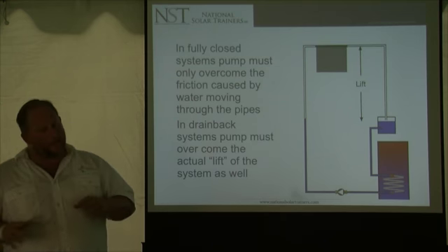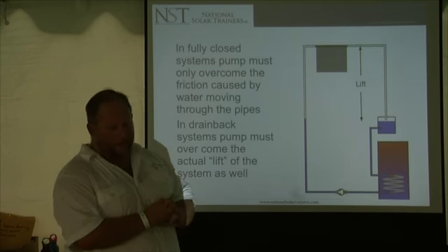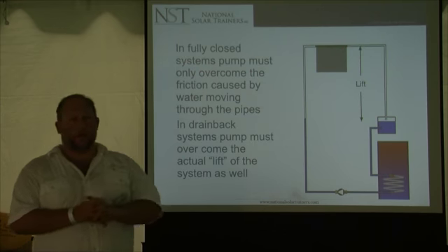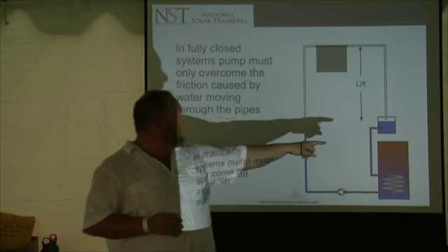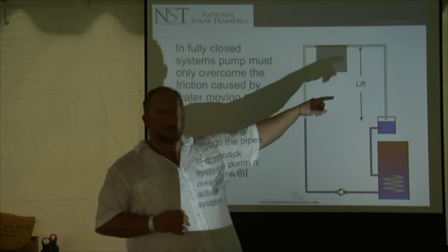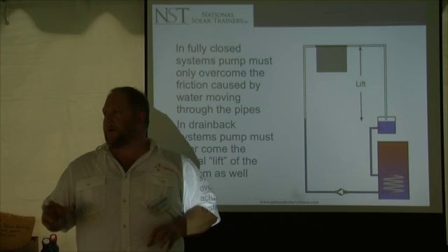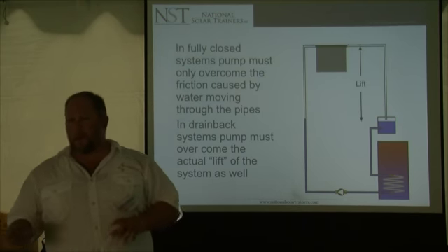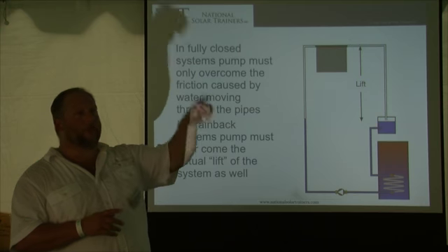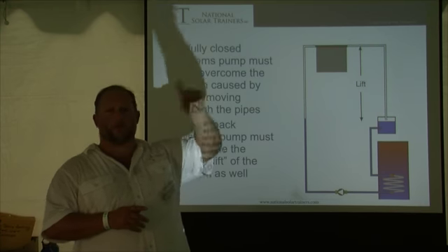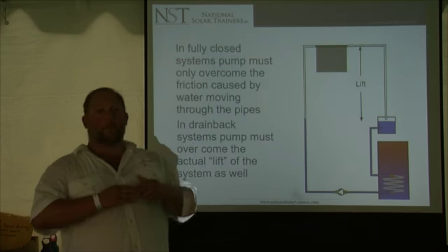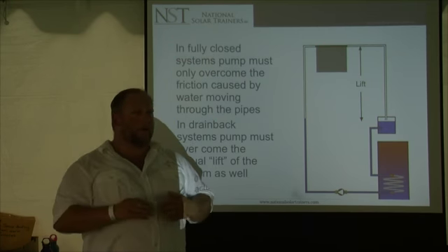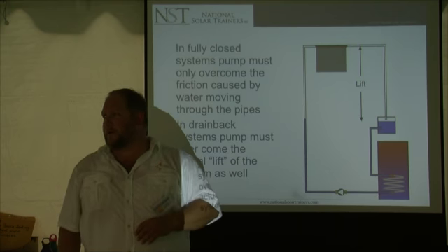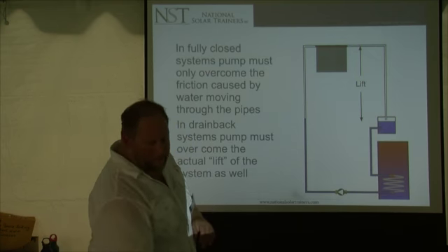Drainback systems are a little bit complex. I'm not going to get into it for homeowners, but basically when the pump turns on in a drainback system, it has to overcome the entire vertical head. So the pump I use for a closed loop system is different than one I'd use for a drainback system, because in a closed loop I'm just circulating, but in a drainback I have to pump it like a fountain, 30, 40, 50 feet in the air. So it requires a much stronger pump.